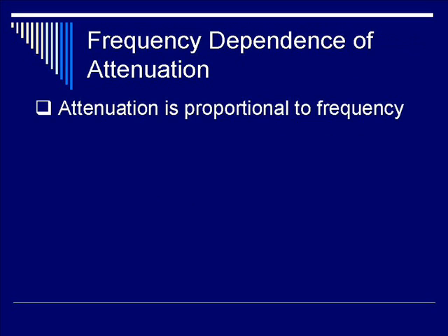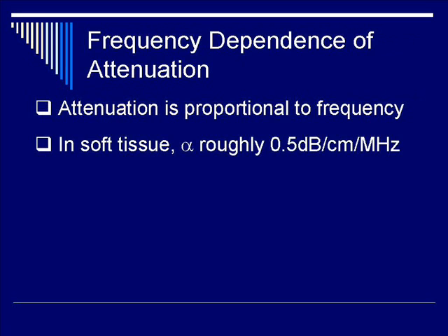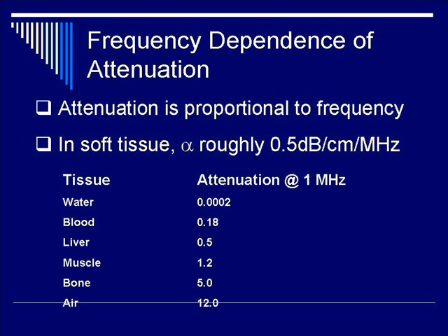Regarding frequency dependence of attenuation: attenuation is proportional to frequency. In soft tissue, alpha is roughly 0.5 dB per centimeter per megahertz. For example, a 1 MHz signal gives 0.5 dB per centimeter, whereas a 2 MHz signal gives twice that attenuation coefficient, becoming 1 dB per centimeter. This table lists the attenuation coefficient for various tissues, ranging from 0.0002 for water, 0.5 for liver, 1.2 for muscle, up to 12 for air.